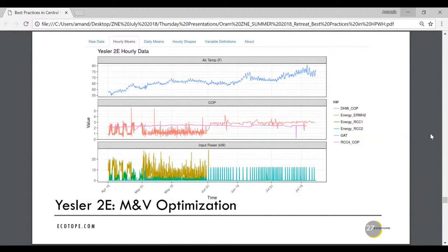If you look at the middle graph, you can see the COP—the purple line is the temperature maintenance, running about 2.5. That heat pump runs pretty much consistently year round, always maintaining the loop. These little stabs down at the bottom show our heat pump cycles—we're running it once every 12 hours, charging up the whole storage tank, running it down, then charging it up again. The big controls change was backing off from being overly conservative.